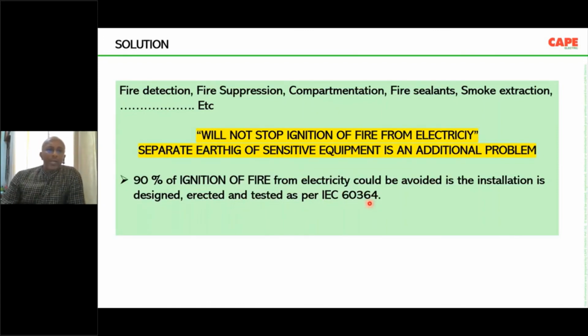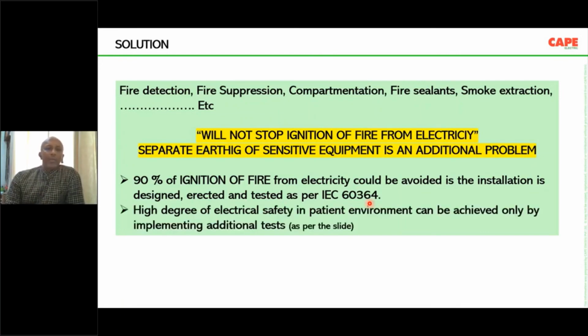The continuity of the conductor, that means test number 1, resistance of the wire, and test number 6, fault loop impedance test. As I said, there are 10 tests. Out of 10 tests, the most important 2 tests are not at all carried out in most of the buildings. And if these tests are carried out, for sure, the design has to take care of it, the installation has to take care of it, and 90% of ignition of fire can be stopped.